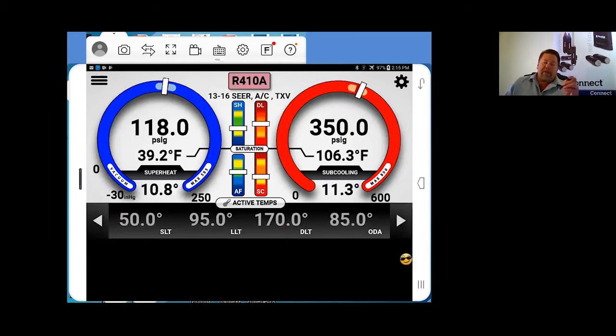Now, outdoor air temperature, when you're taking that at the condenser, make sure you're not getting any reflective heat off of everything. If you're going to take it with an iConnect, for example, or if you're using a 903M, the 12-foot long air probe sensor, don't let that lay on the ground to get any radiated heat. Or if you just washed the coil and it's dried out now, but you've got that probe sitting near water or something like that, let it just get good air temperature that's being brought in around the condenser itself. Just a tip to make sure you're getting your accurate measurements.